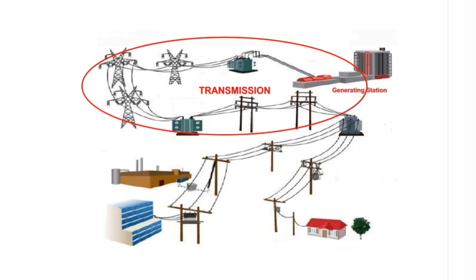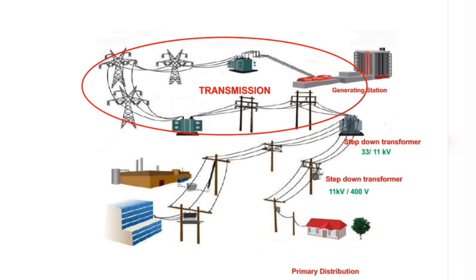The secondary transmission ends at a step-down transformer of rating 66/33 kV or 33/11 kV. From this step-down transformer, the power is transferred to a step-down transformer of rating 11 kV/400 V, located at the point where the users are. The transfer of power from the 33/11 kV transformer to the 11 kV/400 V transformer constitutes the primary distribution.